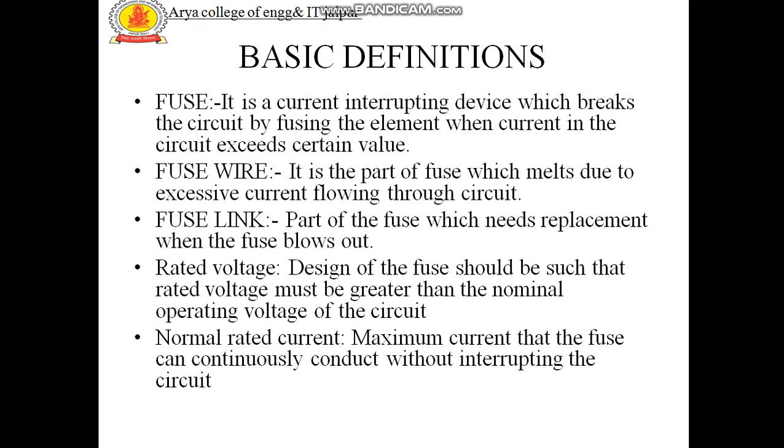Rated voltage: the design of the fuse should be such that the rated voltage must be greater than the nominal operating voltage of the circuit. Normal rated current: the maximum current that the fuse can continuously conduct without interrupting the circuit.